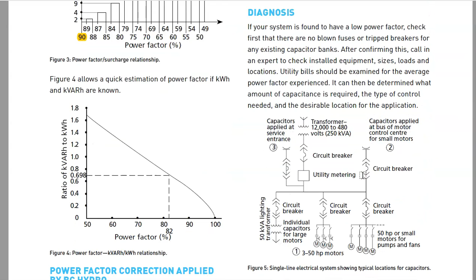There are a couple places they can be applied. First, they show we've got a transformer - 12 kV down to 480 volts. This is my incoming, here's my circuit breaker, here's my metering. They're showing that one place we could do it is apply a large cap, with a circuit breaker in front of it - that's the symbol for it - and there's my cap at the service entrance.